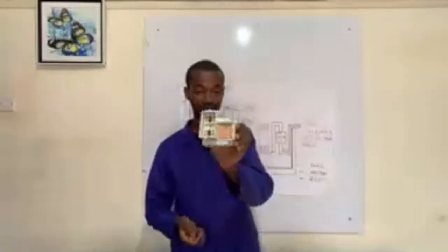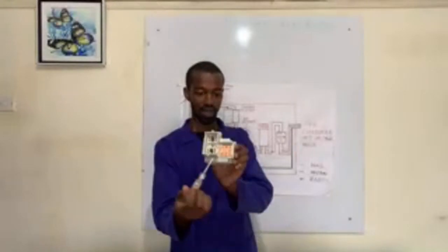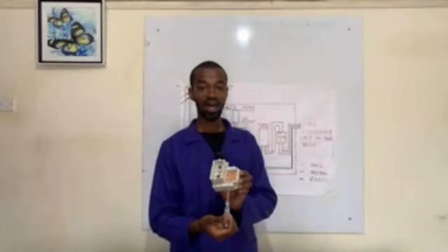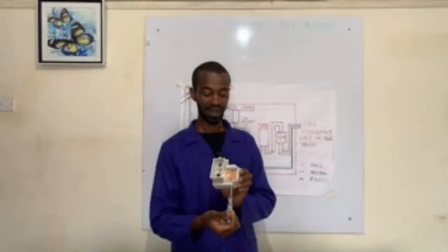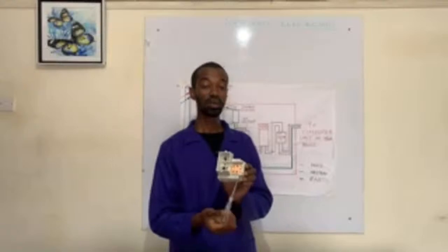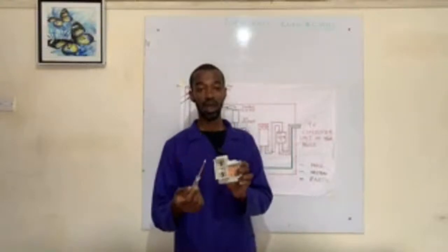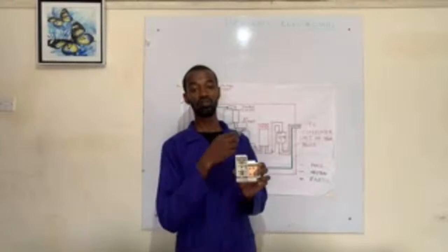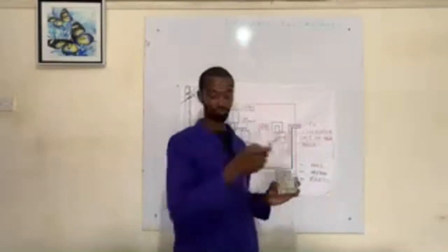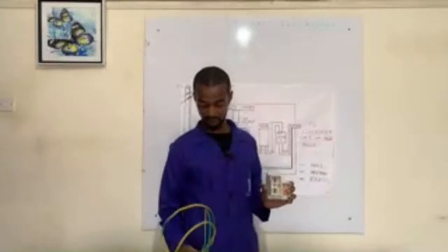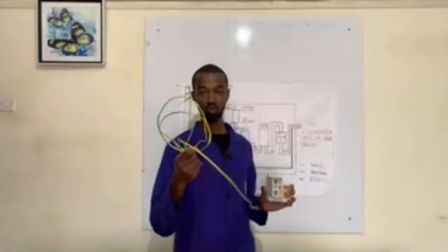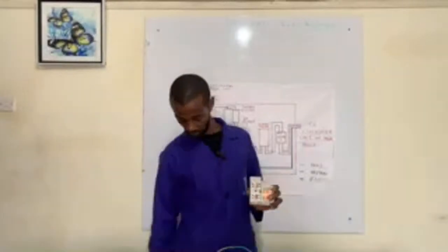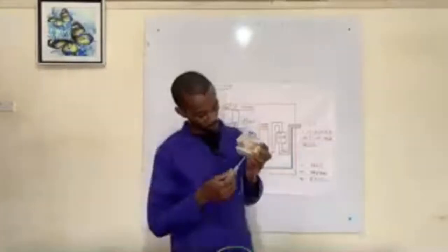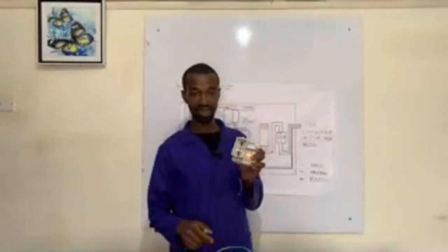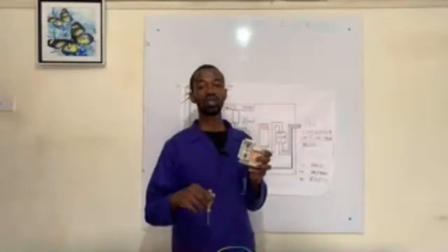Very important part, as you can see, because here now you'll get a looping for the neutral that is outgoing, and an earthing connection which will now be looped to the meter box, as well as the outgoing wire or cable which will now be fed to the consumer unit - that wire is usually in green and yellow stripes, or yellow with green stripes. Now from there, another wire will be connected here, again green with yellow stripes, all the way to the ground.